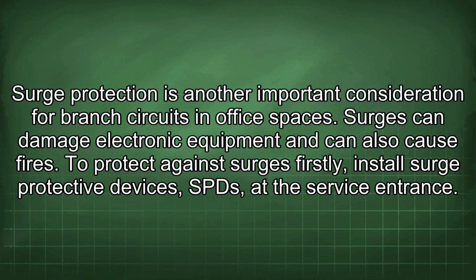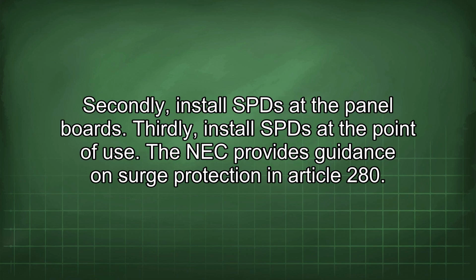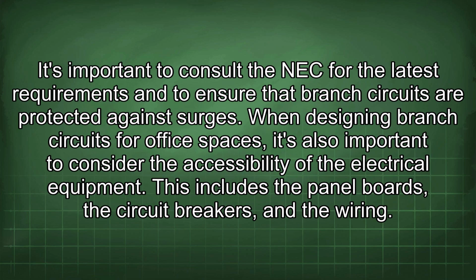Surge protection is another important consideration for branch circuits in office spaces. Surges can damage electronic equipment and can also cause fires. To protect against surges, firstly, install surge protective devices, SPDs, at the service entrance. Secondly, install SPDs at the panel boards. Thirdly, install SPDs at the point of use. The NEC provides guidance on surge protection in Article 280. It's important to consult the NEC for the latest requirements and to ensure that branch circuits are protected against surges.